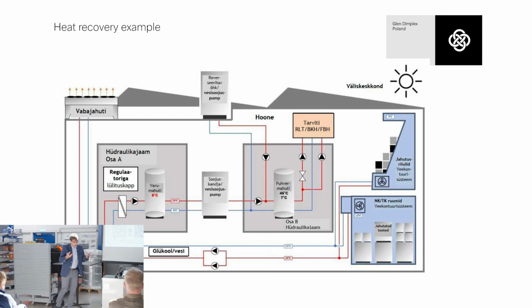And let's talk about the main topic for today: the heat recovering system for the stores, for the magazines. This is the principal diagram with the idea. We have the cabinets in the store, which need to be cooled, and we have the loop. Then we collect this energy in the buffer tank, and via the heat pump we transfer the energy. We raise the temperature and transfer the energy to the secondary buffer on the upper side, and from this buffer we can spread this energy to the building using typical installations, for example fan coils or whatever, or heaters built into the ventilation units.